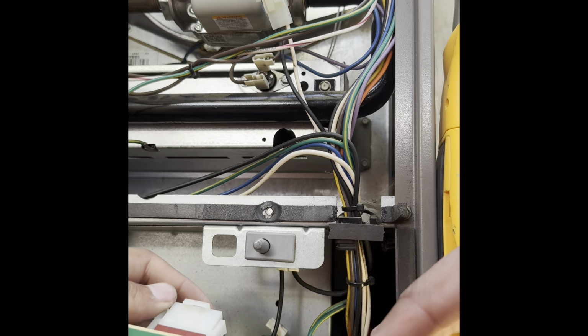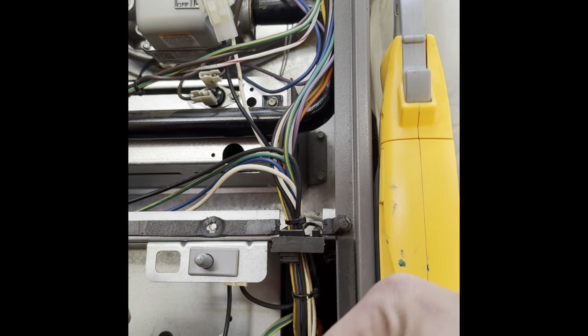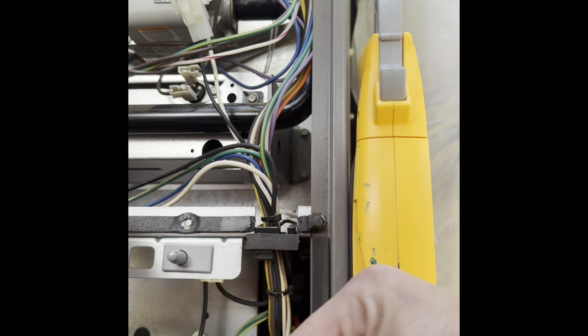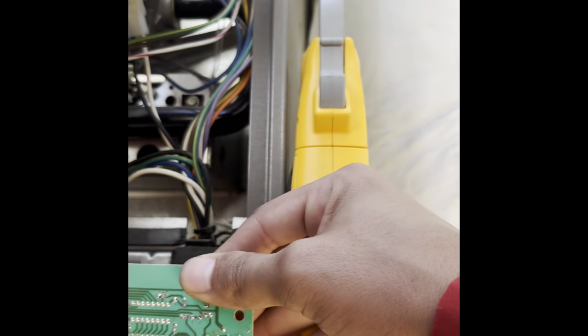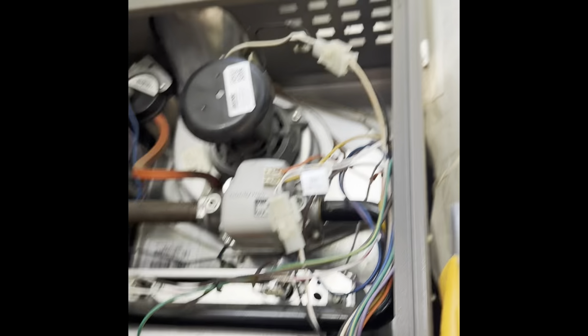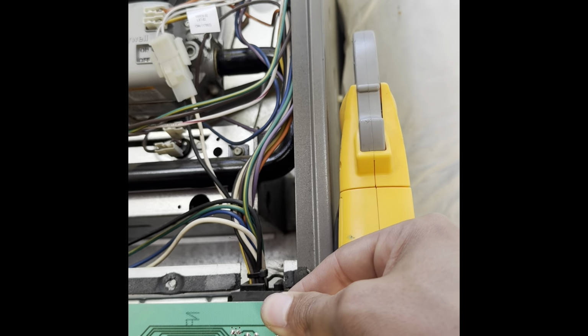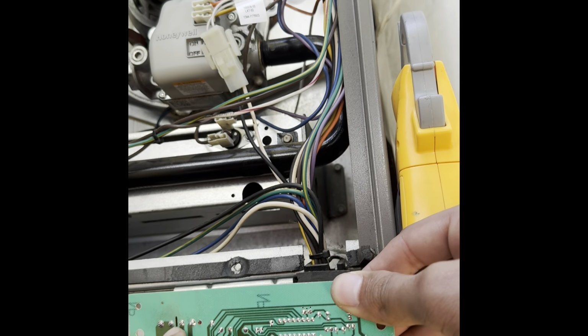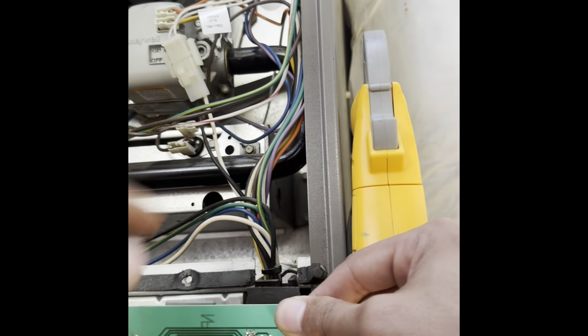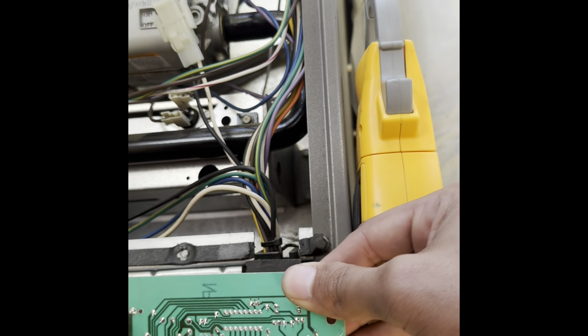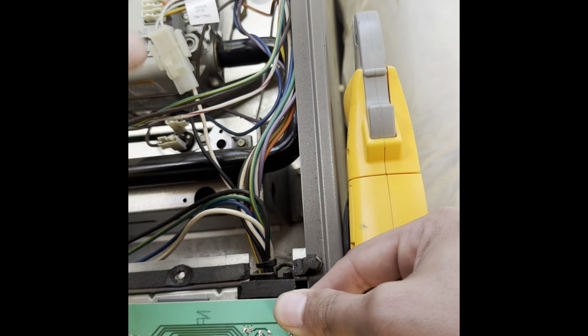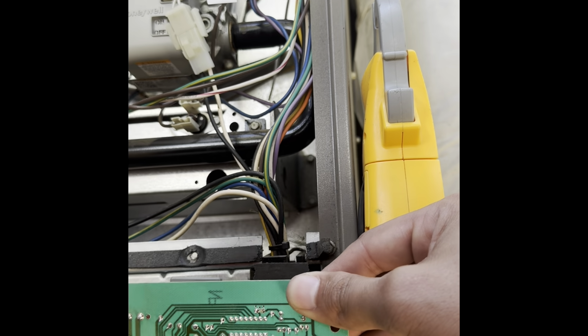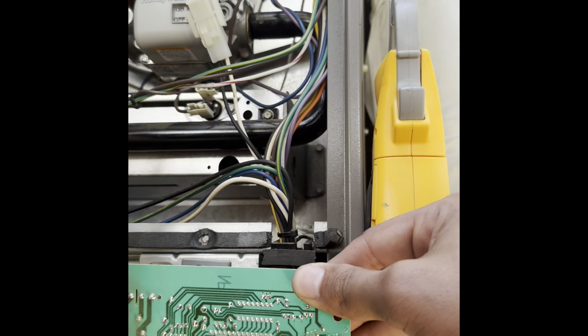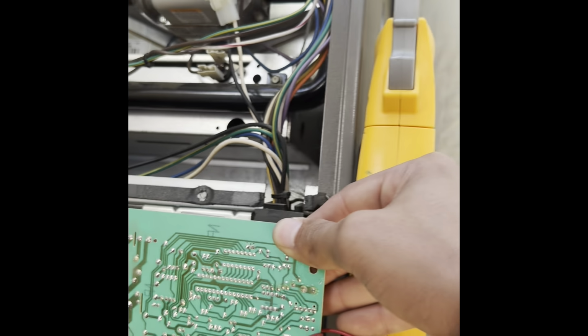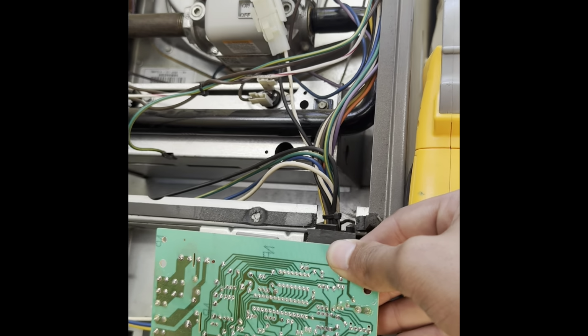This is the connection that goes to the igniter - one black and one white wire go to the igniter, and the other goes to the inducer. So this is this connection right here. If these connections fail, like you can see they're starting to fail, it won't make proper connection with the board, and the board won't be able to get a good connection to ignite the igniter or the inducer. That's the reason why we like to take a look at the board.